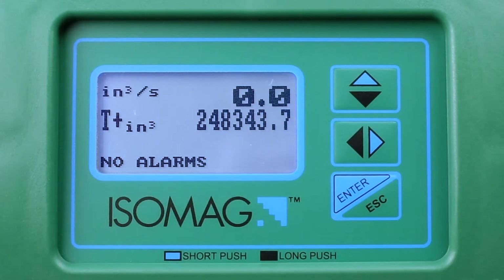This video will explain how to set the flow rate, full scale and 4-20 mA output range. The flow rate unit of measure and scale range are reference points for the measure cutoff and flow rate alarm thresholds. The analog range defines the 20 mA flow rate value. For the MV series of converters, the procedure is easily made.